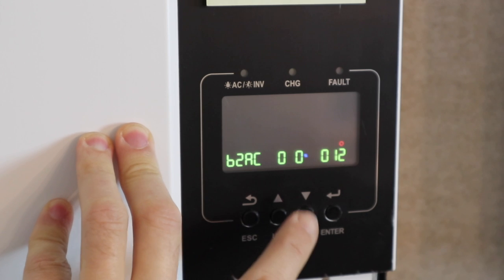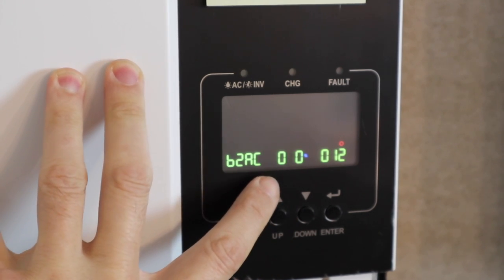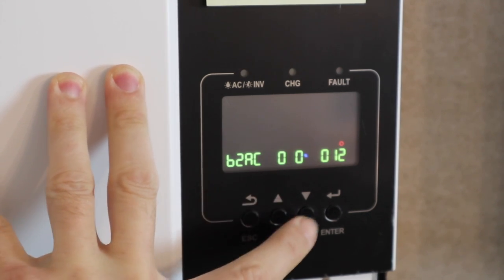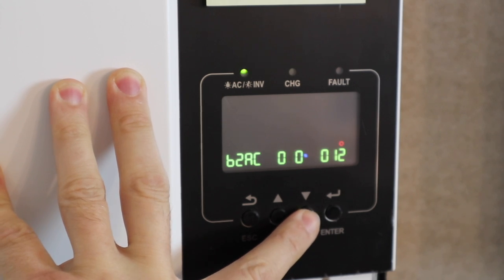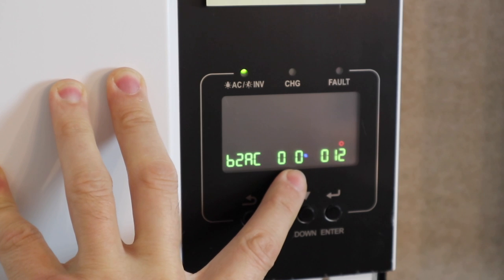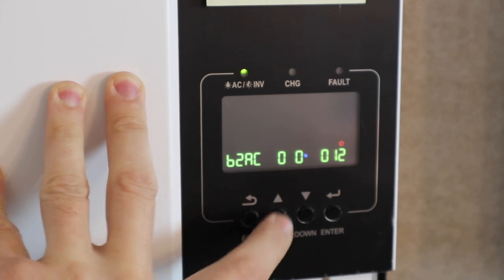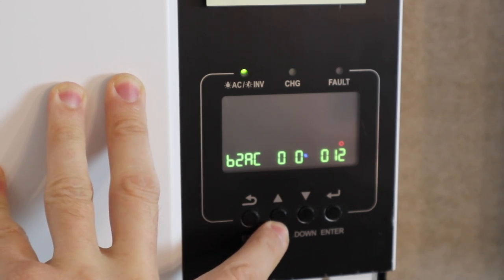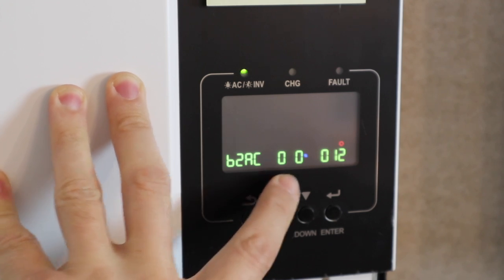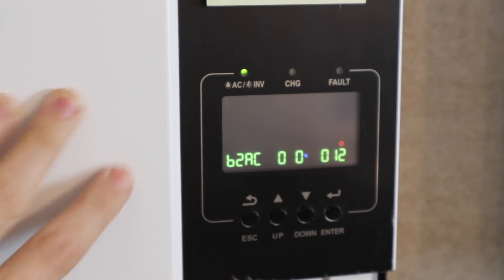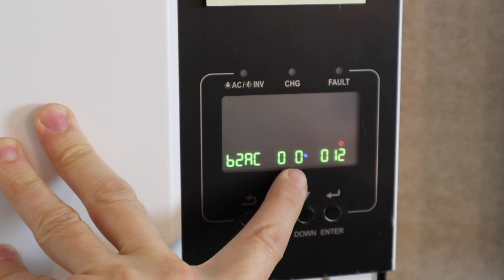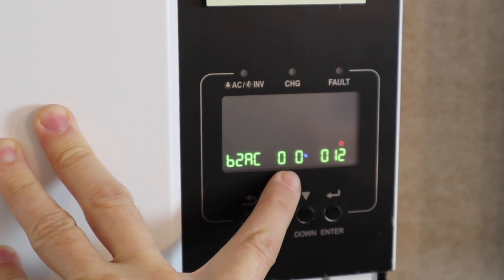So setting number 12 is where the batteries discharge to. What percentage? Obviously, lithium batteries, you can discharge down to 0%. But that is going to kill the life of your battery faster. So it's recommended that you go down to 20%. But for us, we live in a decently sunny area. We're gonna actually go to 30%. So our batteries will not discharge below 30%.